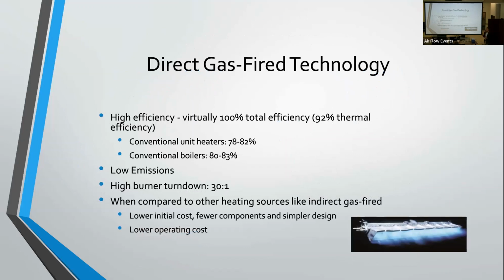So let's quickly touch base on direct fire heating. This is basically the most efficient means of heat that you can provide for our industry, because every BTU of gas that gets burnt ends up in the heated airstream and goes into the space. So overall total efficiency of virtually 100%, or 92% thermal efficiency when you account for the water vapor generated during the combustion process, but still extremely high when you compare it to conventional unit heaters that are about 78 to 82% efficient, or conventional boilers that are around 80 to 83% efficient. So significantly more efficient.